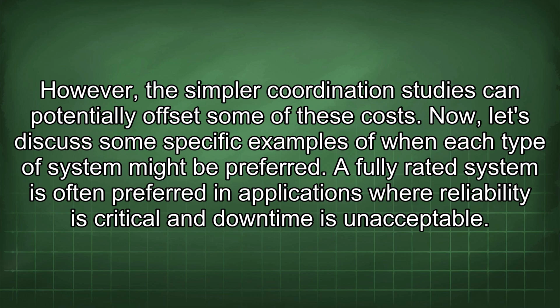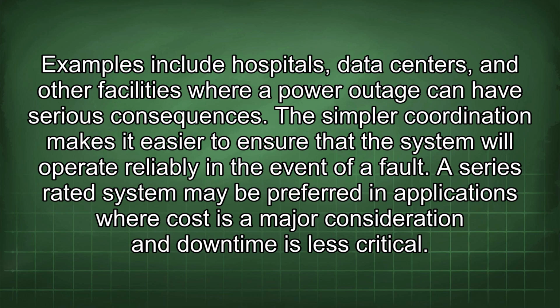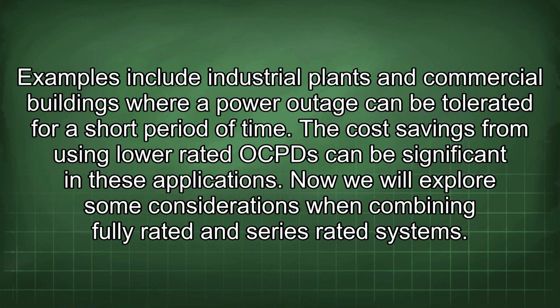Now, let's discuss some specific examples of when each type of system might be preferred. A fully rated system is often preferred in applications where reliability is critical and downtime is unacceptable. Examples include hospitals, data centers, and other facilities where a power outage can have serious consequences. The simpler coordination makes it easier to ensure that the system will operate reliably in the event of a fault. A series-rated system may be preferred in applications where cost is a major consideration and downtime is less critical. Examples include industrial plants and commercial buildings where a power outage can be tolerated for a short period of time.